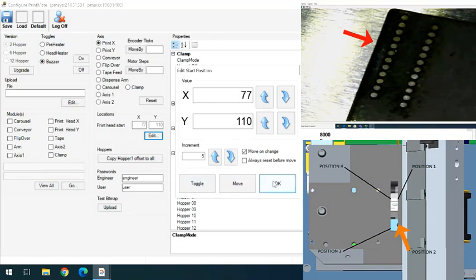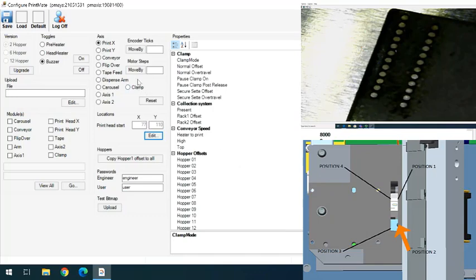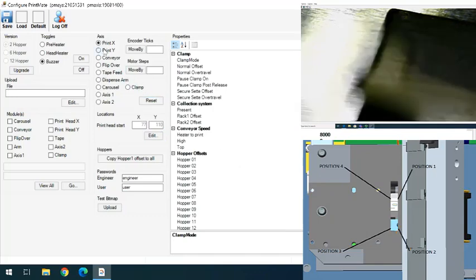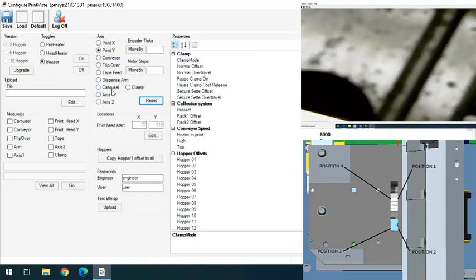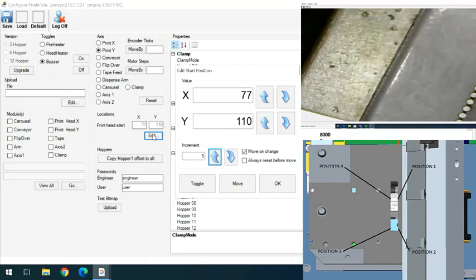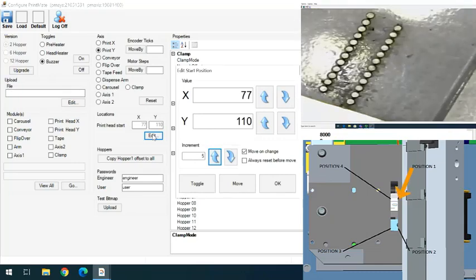We press OK. We want to reset X and reset Y. We want to edit our locations window and verify calibration with toggle 2 more times. We select edit in locations, and we check position 1. Position 1 is still 1 pin width from the platen on the y-axis.